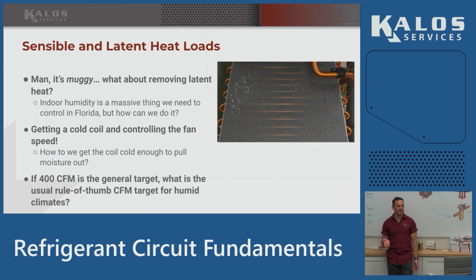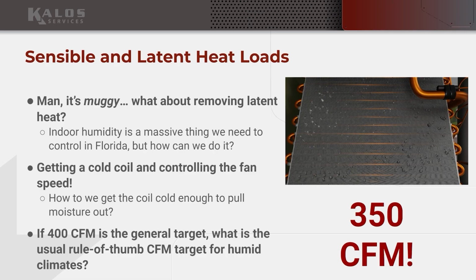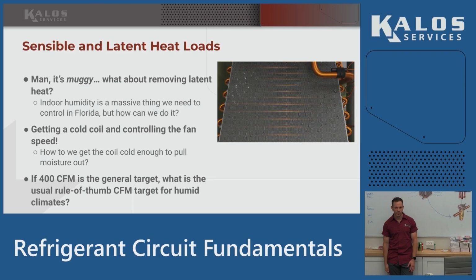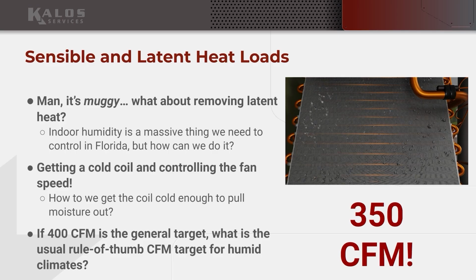So by running our fan speed lower, letting that air hang out over the coil a little bit longer, we're getting more humidity out of the air, and we're hitting our target temp splits. So in Florida, your target CFM is about 350 per ton. You can play with that depending on the system, but that's the basic idea. We're trying to dehumidify much more than other markets, because for our comfort, that's a huge factor. What else did I hit here? Yeah, 350 CFM is our target.